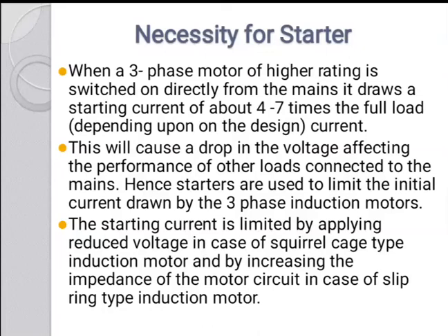When a three-phase motor of higher rating is switched on directly from the main supply, it draws a very high starting current, which is about 4 to 7 times the full load current. Imagine if the full load current is 10 amps. Then it's 4 to 7 times, around 40 to 70 amps it will draw whenever you switch on the three-phase induction motor.